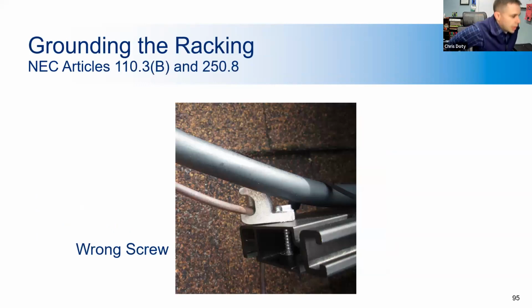So here we have a situation where they bonded the rails themselves, and you have to do that, and it's accomplished through a lay-in lug like the one pictured here. However, the lug is not installed with a screw that is listed for bonding purposes, and that's typically done with a finely threaded machine screw. The code requires that a minimum of 2 threads are in connection with the metal, and this is a self-tapping screw with pretty coarse threading. So this would fail for that reason. It doesn't have a good enough connection to the rails, so it can eventually fail.